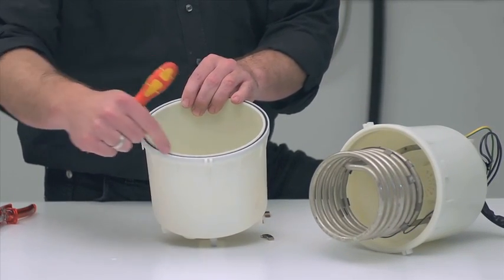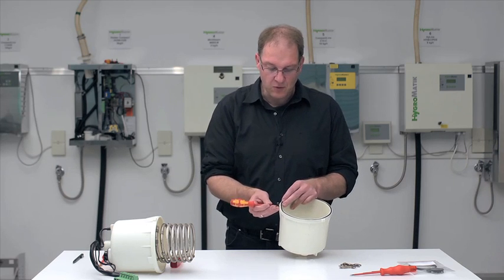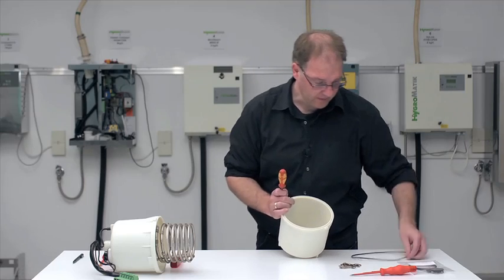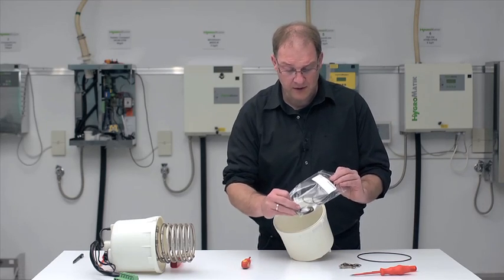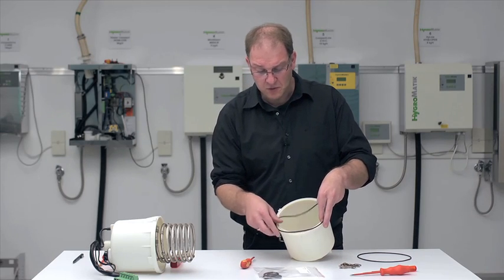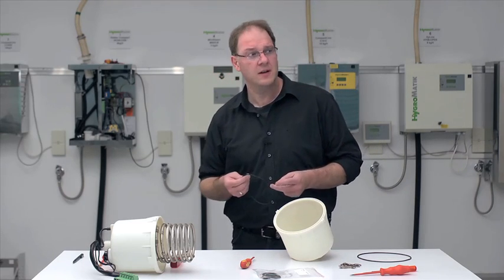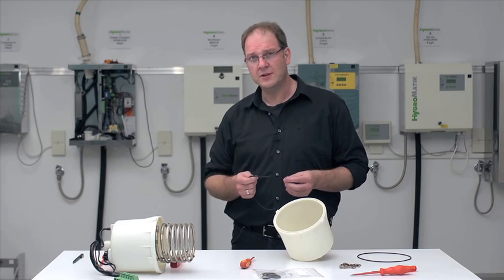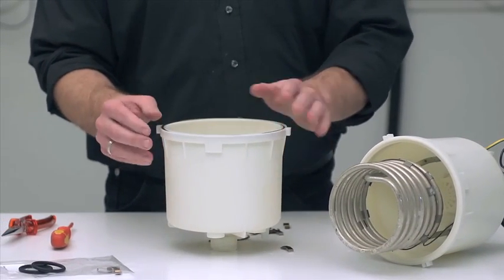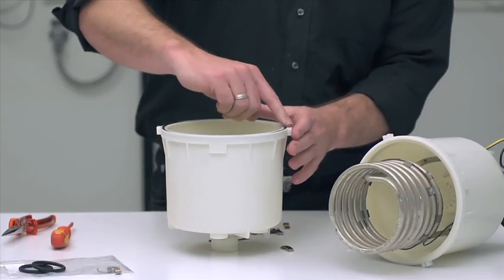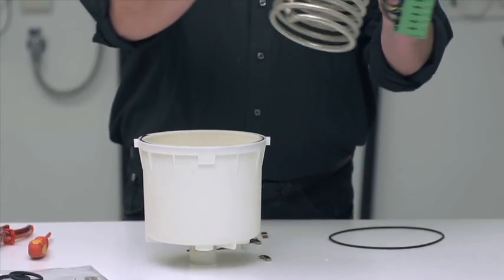I do, of course, have to replace the O-ring here in the flange area. To remove it, you can take a small slotted screwdriver and then pry up the O-ring and pull it out. We have an O-ring set that we always recommend using during maintenance. In the O-ring set you will find the large O-ring for the cylinder flange and two other smaller O-rings. These we will use on top for the connection to the steam hose adapter and on the bottom for the connection to the base. Inserting them is quite simple. Here too, of course, the area where the O-ring is placed, properly clean of deposits, so it will then tightly seal later on. At this point we can reconnect them.